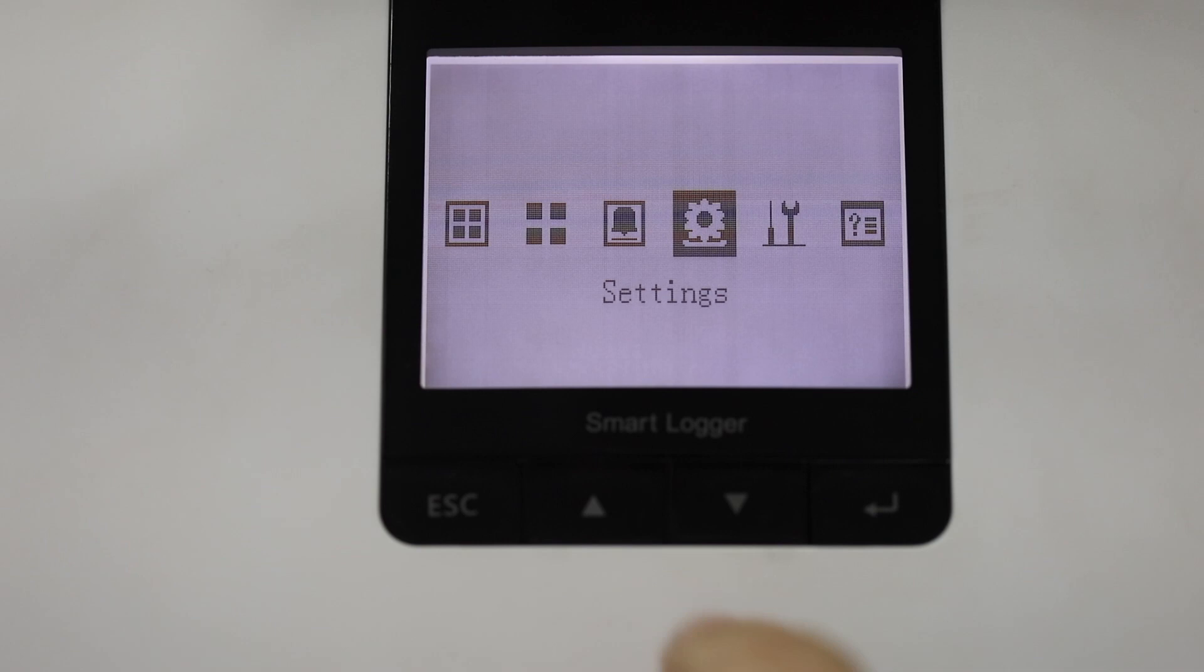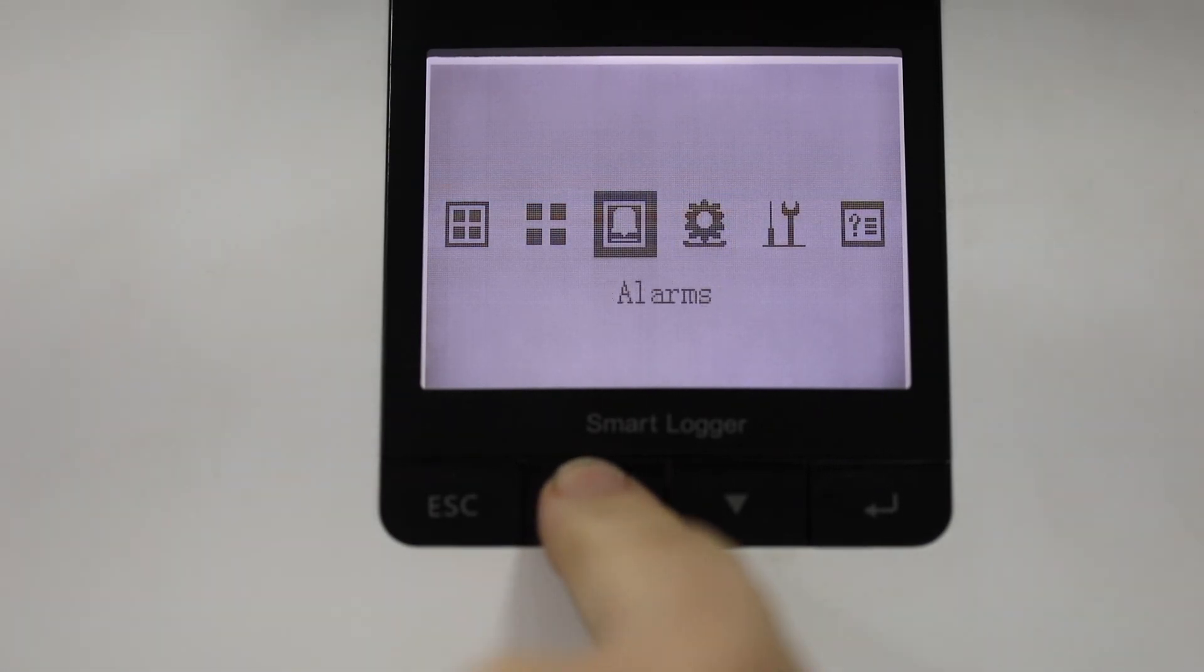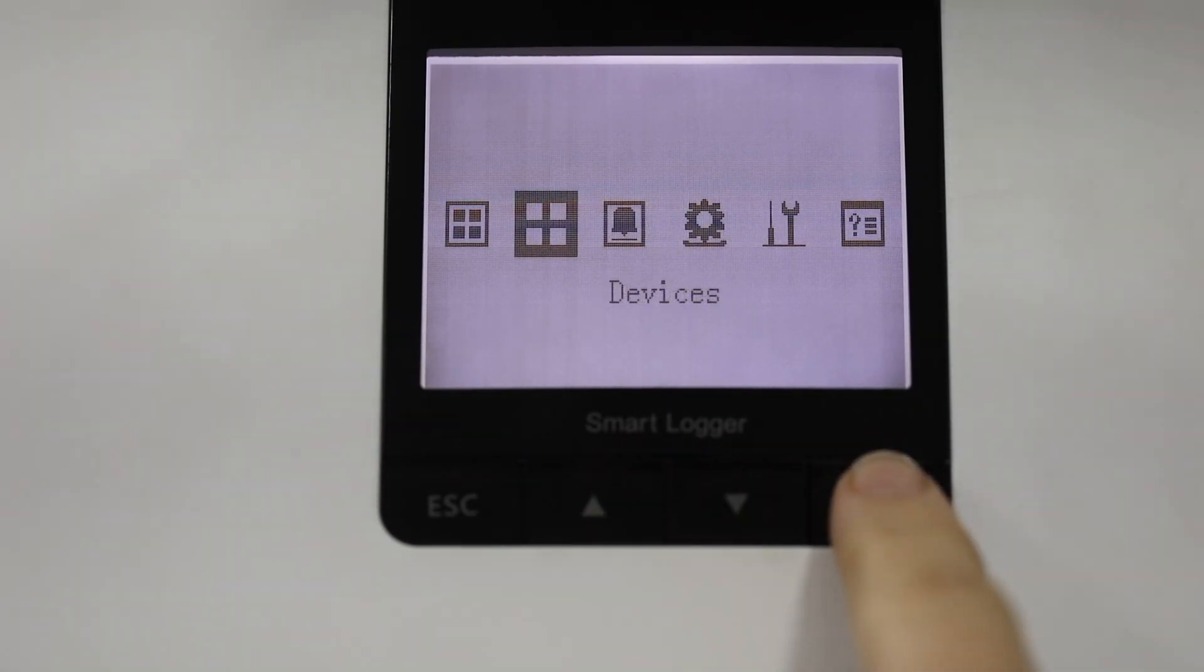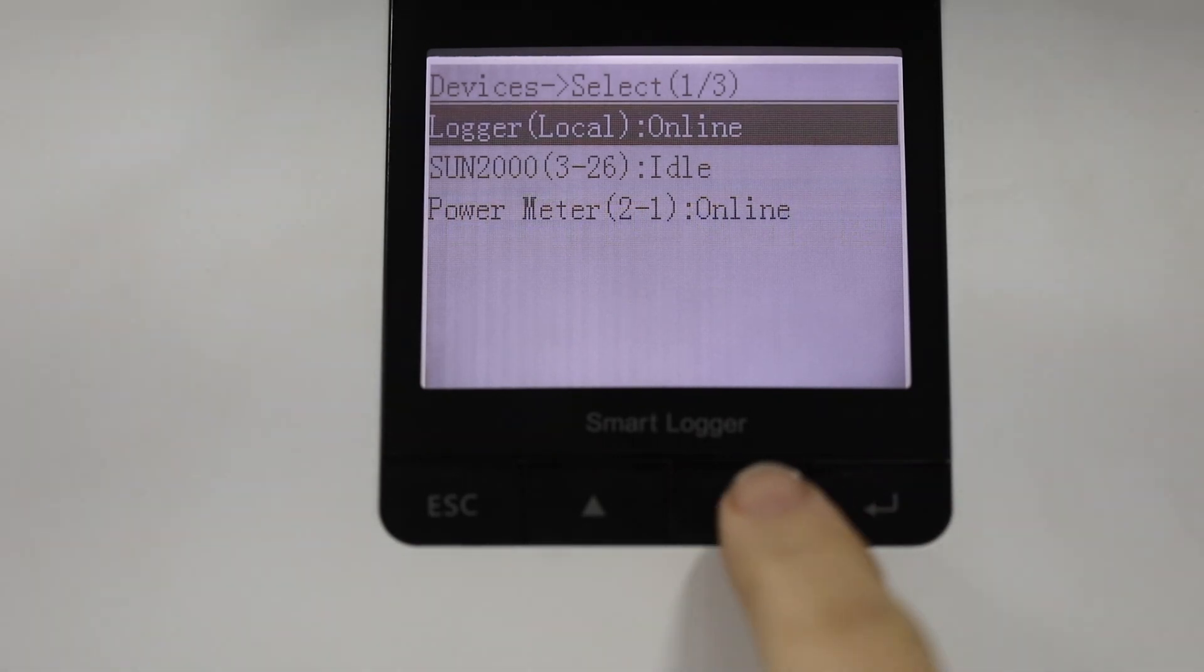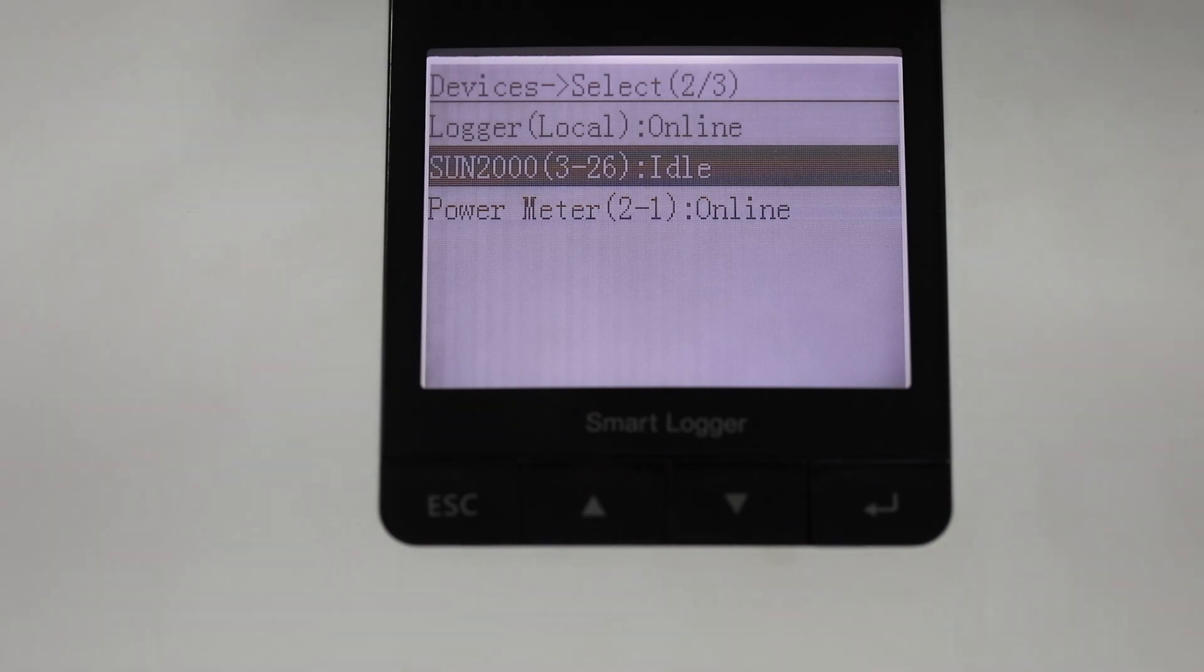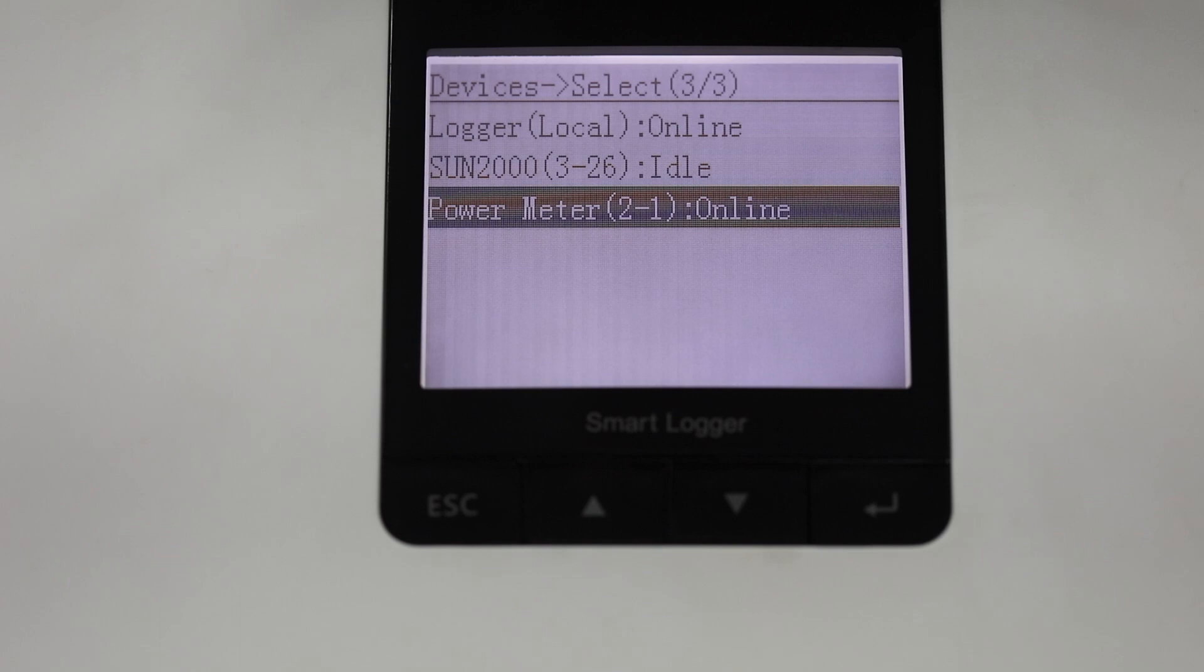Now we're going to go and add the meter to the list of devices. Now I've already done this so you'll see that we've got the inverter which is the Sun 2000. It is detected automatically but the power meter you need to add manually. So you choose manual add, choose power meter and then accept.